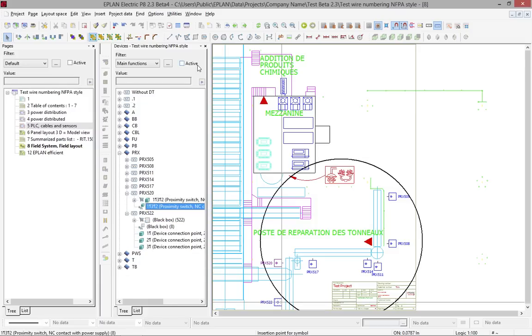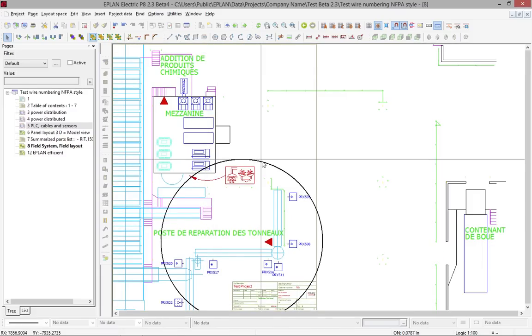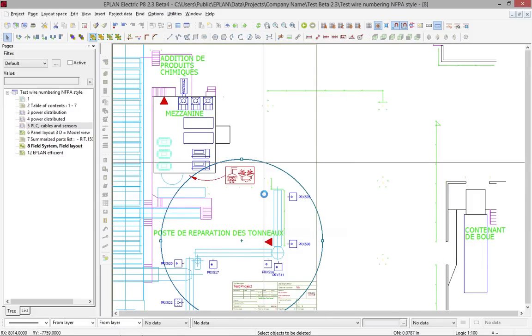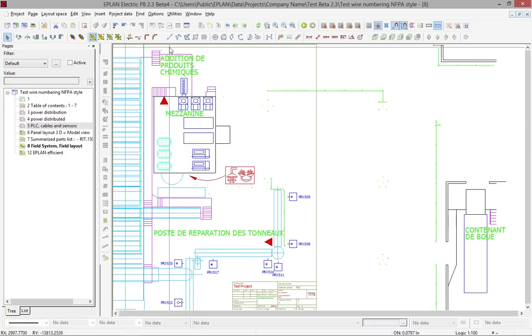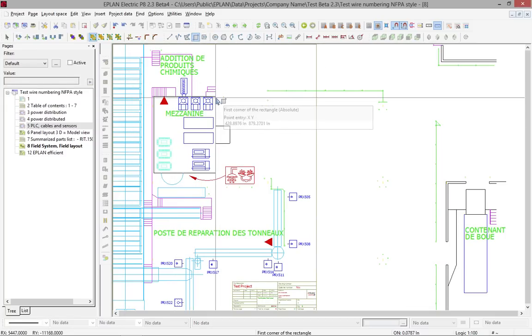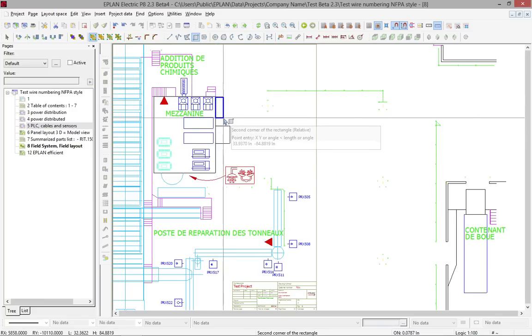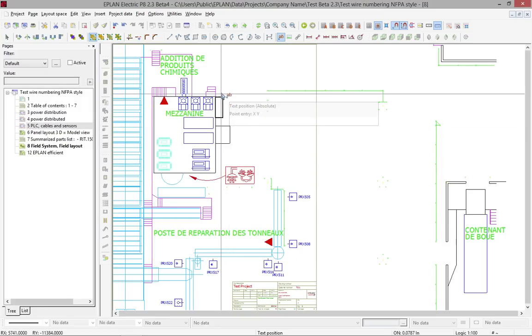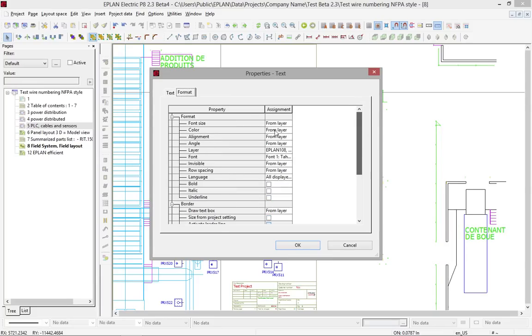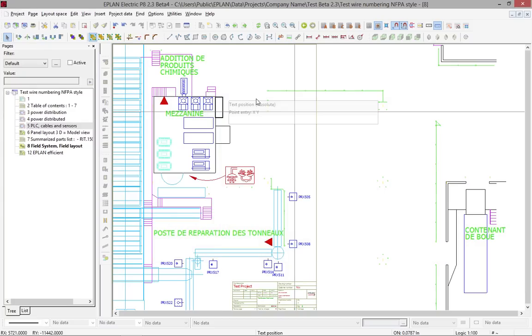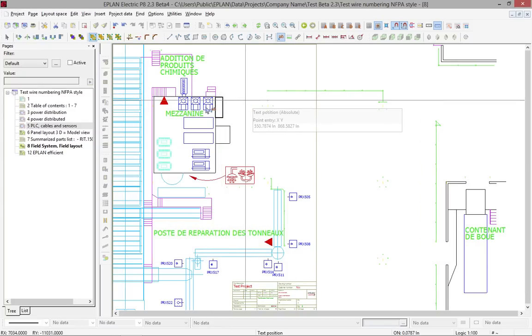The next and second step is actually to define the different cable trays. The cable trays will start at the panel somewhere that you place. So this panel you can represent it really just with a simple rectangle. The rectangle may start basically here - this is where physically you will locate your panel. If you want to add some text, you have to add this text in here. The size of the text here you can see that it was really small. Why? Because we are in a 1 to 100 scale.